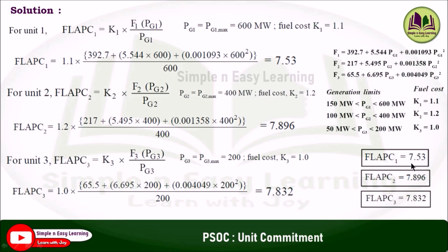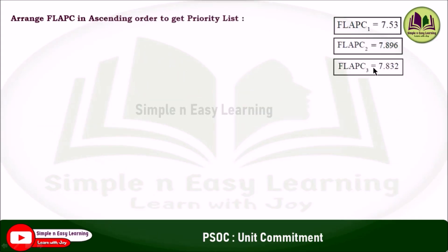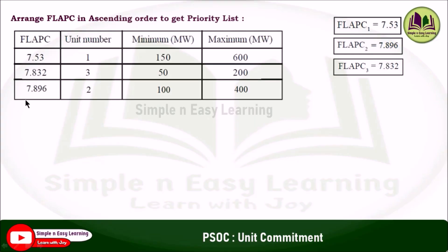So FLAPC_1 is 7.53, FLAPC_2 is 7.896, and FLAPC_3 is 7.832. Considering these three values, arrange the FLAPC in ascending order to get the priority list. In ascending order: first 7.53, then 7.832, then 7.896 — meaning unit 1 is first priority, unit 3 is second, and unit 2 is third.